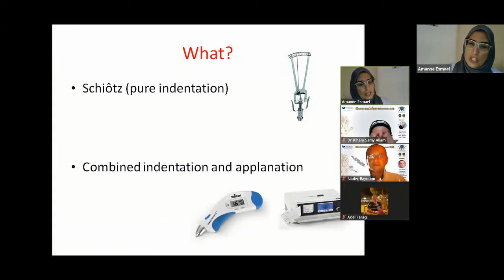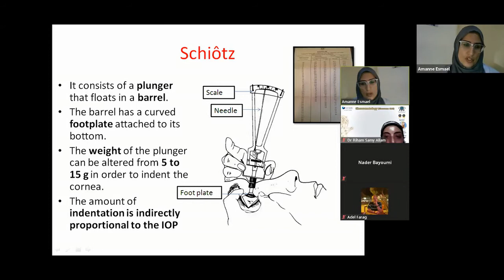It has a plunger that is encased in a barrel, and the barrel has a foot plate that is concave and rests on the cornea. As the plunger moves, its movement is transmitted to the needle, and this gives us a number on a scale. Several weights can be mounted up here to be used for different measurements, especially with the higher intraocular pressures. So the amount of indentation is indirectly proportional to the intraocular pressure.